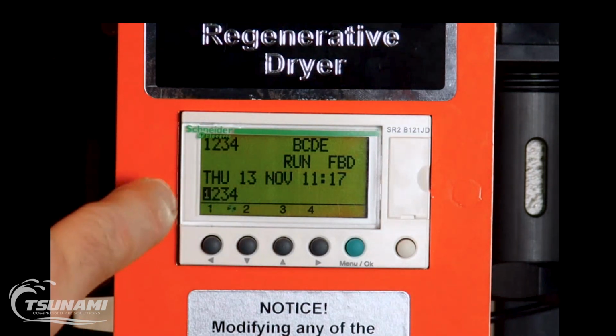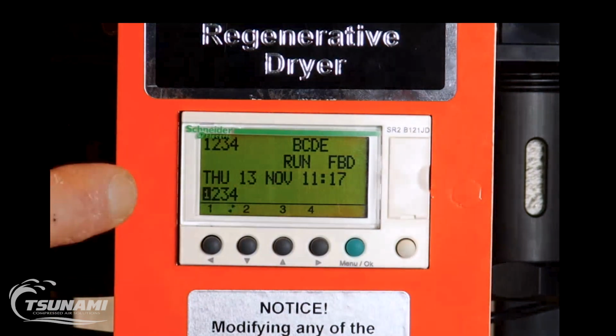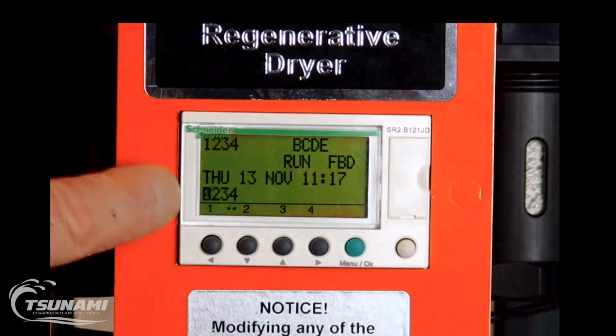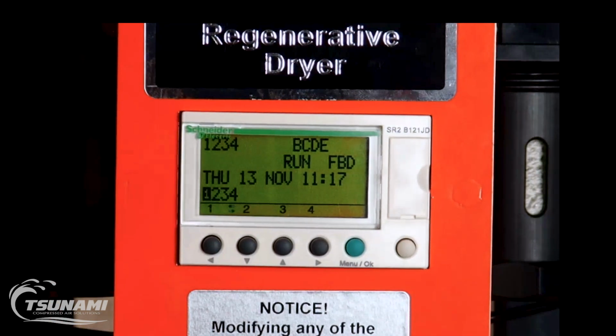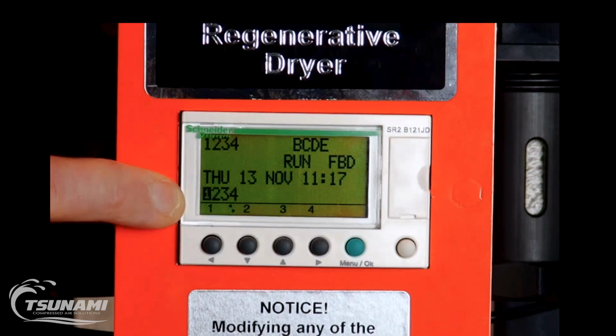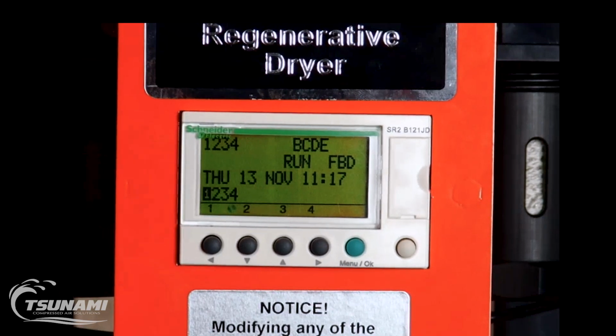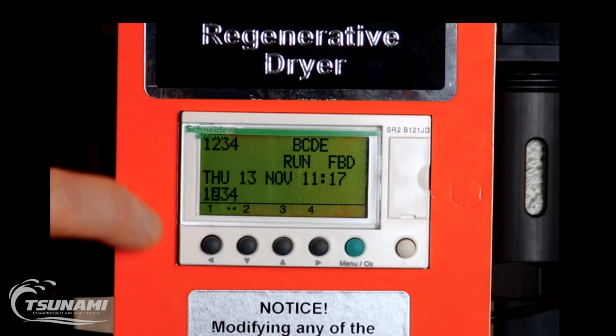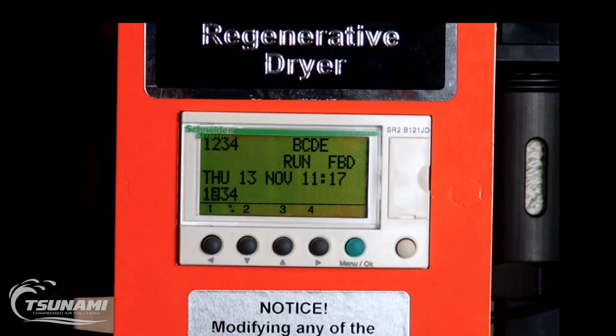These 4 numbers down below, 1, 2, 3, 4, that are close together, those are the output signals that are going on. So right now we are sending an output signal to tower 1, which would be our left tower. And that would be putting the left tower into regeneration, and the right tower would be doing the drying of that. As you can see, it just cycled over, so we're at that 2-minute period. It moved over. Now it's sending a signal to tower 2, which would be the right tower.